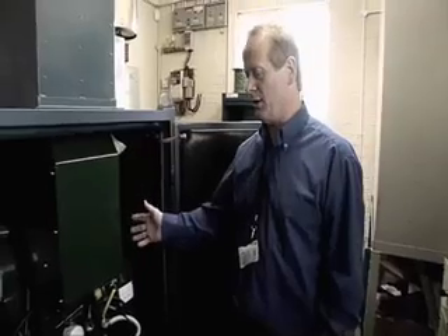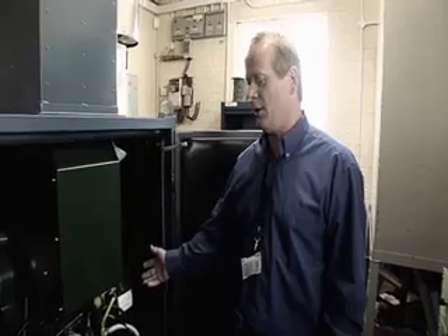We arrive on site, check that the oil levels are correct, check for any leakages, and check the starter batteries are in good condition. I maintain roughly 25 sites which all have generators, but nationally all BT sites are backed up with a standby generator.